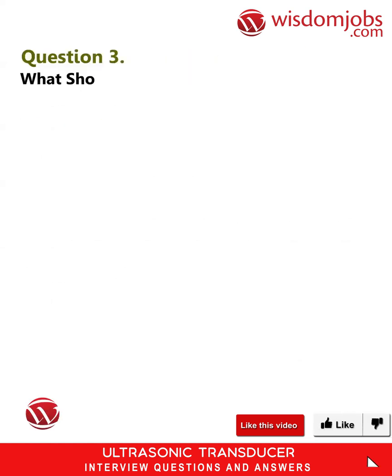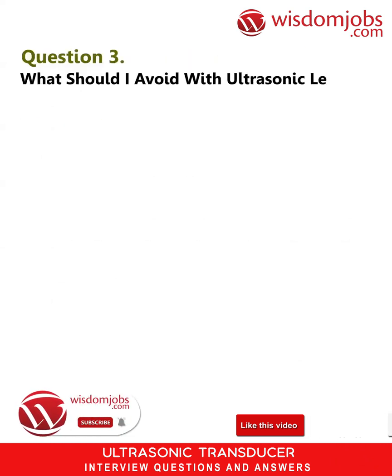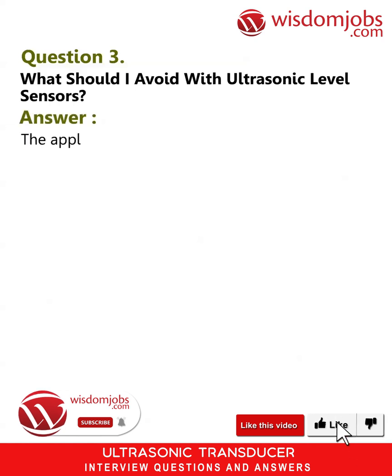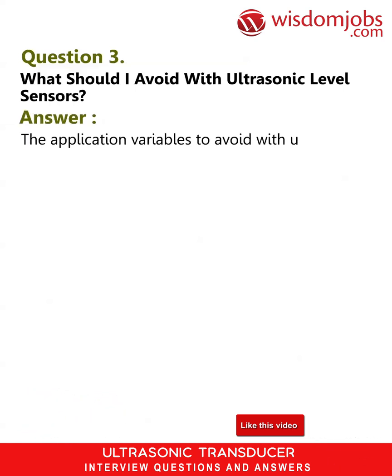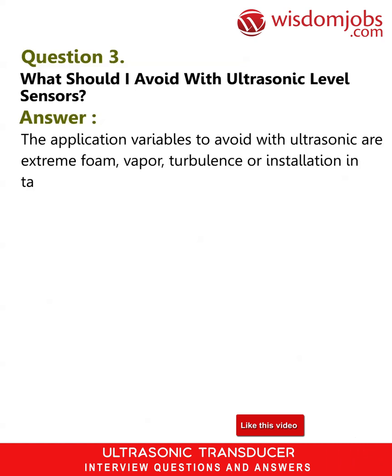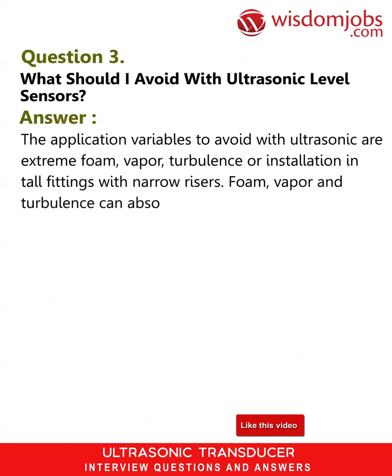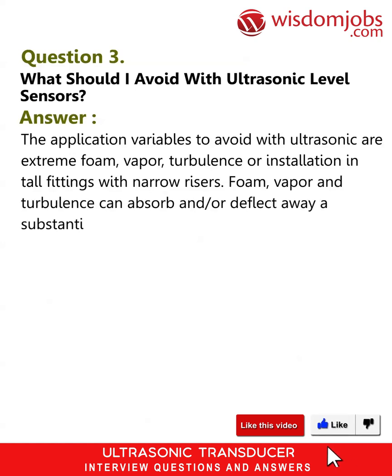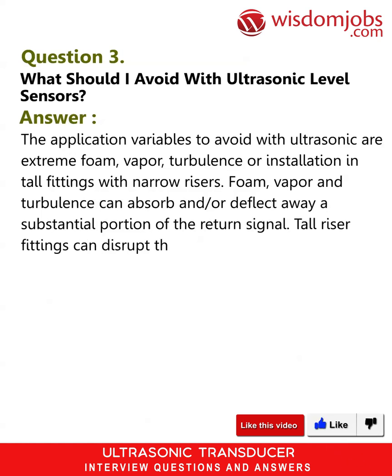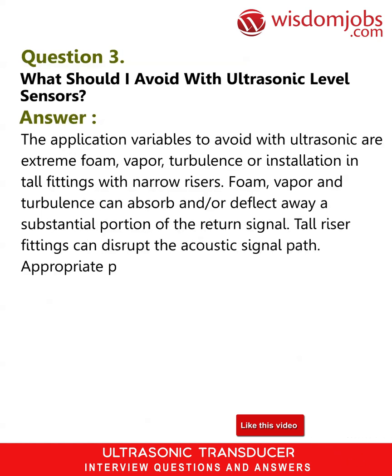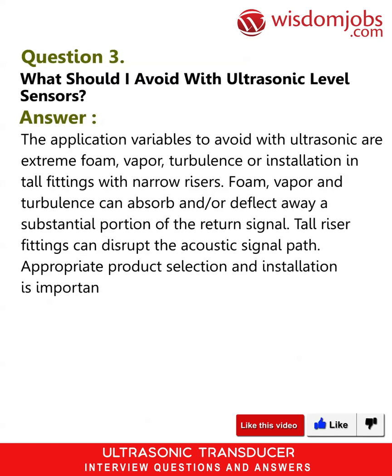Question 3. What should I avoid with ultrasonic level sensors? Answer. The application variables to avoid with ultrasonic are extreme foam, vapor, turbulence or installation in tall fittings with narrow risers. Foam, vapor and turbulence can absorb and/or deflect away a substantial portion of the return signal. Tall riser fittings can disrupt the acoustic signal path. Appropriate product selection and installation is important.